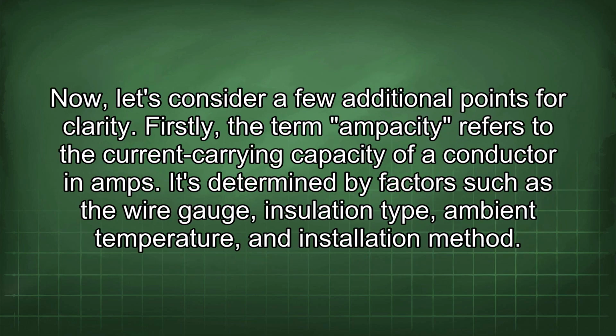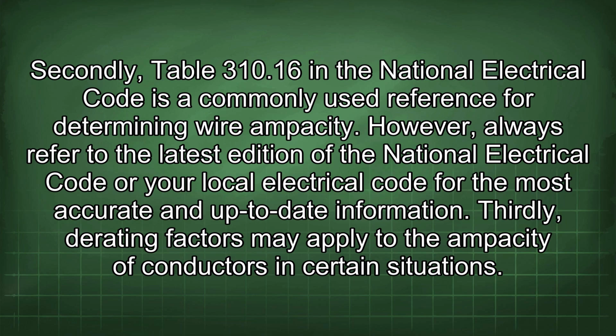Now, let's consider a few additional points for clarity. Firstly, the term ampacity refers to the current carrying capacity of a conductor in amps. It's determined by factors such as the wire gauge, insulation type, ambient temperature, and installation method. Secondly, Table 310.16 in the National Electrical Code is a commonly used reference for determining wire ampacity.